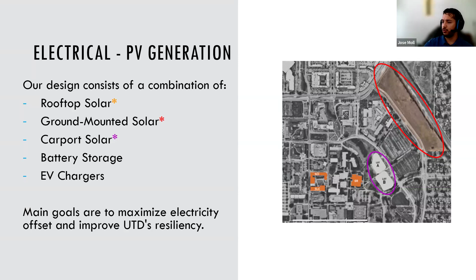Here we can see a bit more detail about the solar sizing for our system. We have 2 main types of systems: those with grid following inverters and those with grid forming inverters. With the aggregate PV sizing being around 2.5 megawatts, about a quarter of the energy production capacity comes from our rooftop systems using grid following inverters, and the rest of the system uses grid forming inverters. This ratio allowed us to benefit from the use of grid forming inverters while still having the flexibility to include grid following ones.